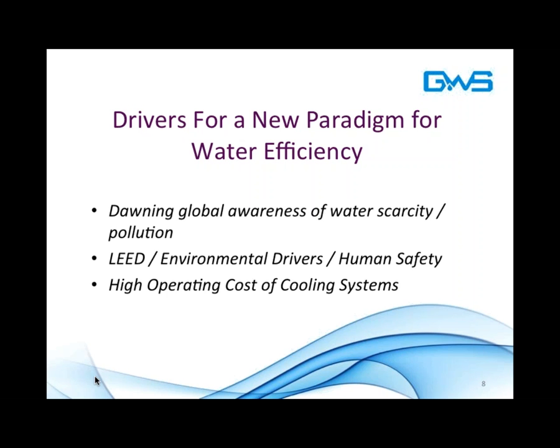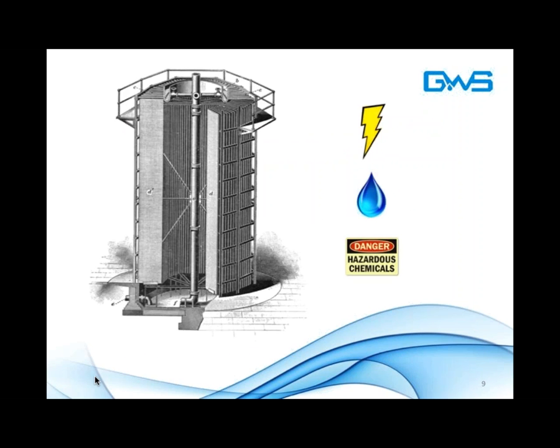I don't know if LEED is still a gold star program and it's being pursued widely, although engineers tell me that in fact the standards are being pursued widely, but the marketing credential that it provides may not be as relevant. Lastly, the high operating cost of cooling systems is something that building operators and managers, I think, are beginning to wake up to. Typically, as you all know, cooling towers are out of sight, out of mind. Most people are focused on the cost of water in potable uses in the building: dishwashers, laundry, water and sinks, flushing toilets. But the reality is that water in commercial and industrial buildings is often consumed in large quantity by the cooling systems that occupy them.